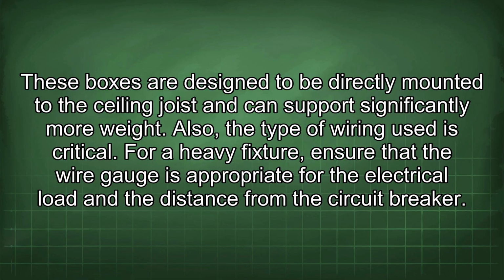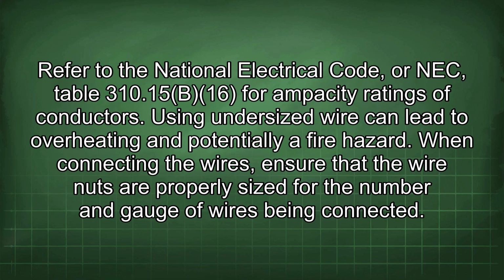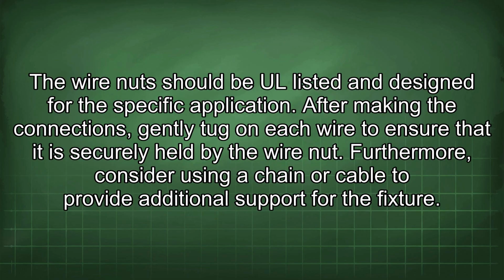Also, the type of wiring used is critical. For a heavy fixture, ensure that the wire gauge is appropriate for the electrical load and the distance from the circuit breaker. Refer to the National Electrical Code, or NEC, Table 310.15(B)(16) for ampacity ratings of conductors. Using undersized wire can lead to overheating and potentially a fire hazard. When connecting the wires, ensure that the wire nuts are properly sized for the number and gauge of wires being connected. The wire nuts should be UL listed and designed for the specific application.